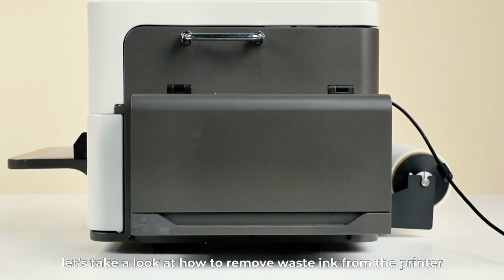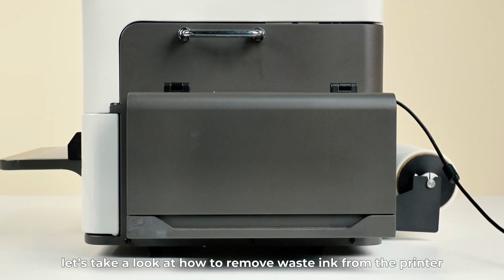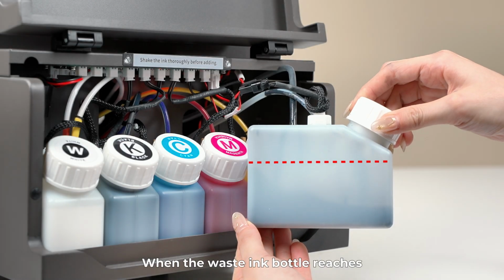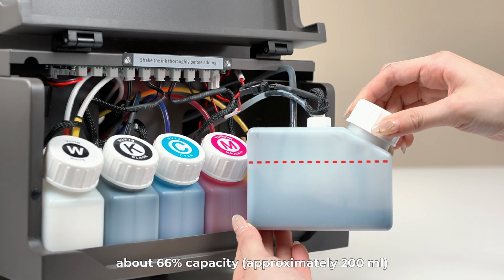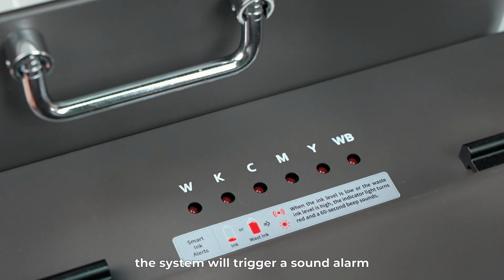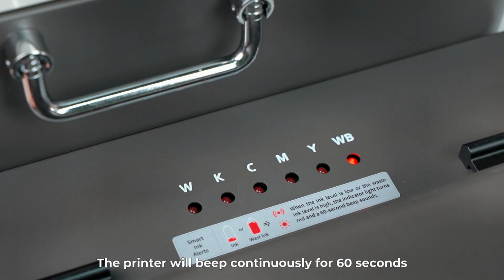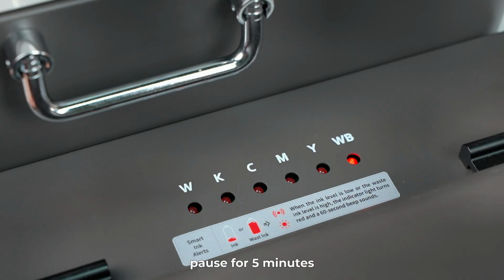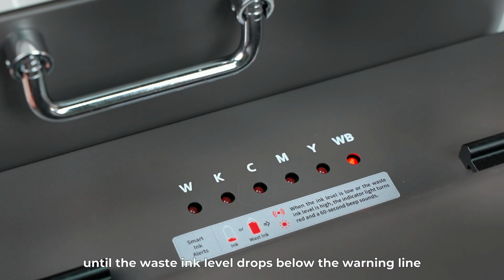Finally, let's take a look at how to remove waste ink from the printer. When the waste ink bottle reaches about 66% capacity, the system will trigger a sound alarm. The printer will beep continuously for 60 seconds, pause for 5 minutes, and then beep again for another 60 seconds. The alert will continue to repeat until the waste ink level drops below the warning line.